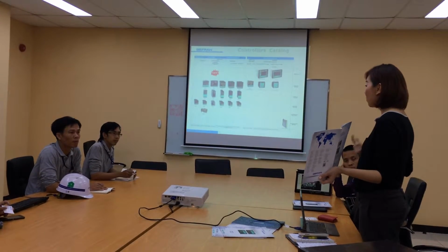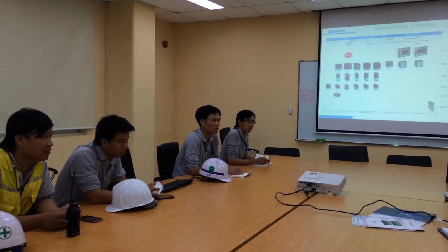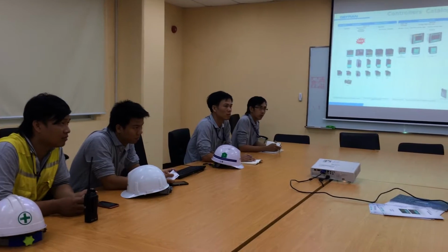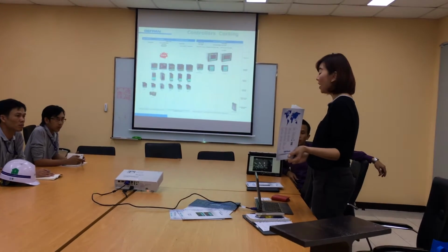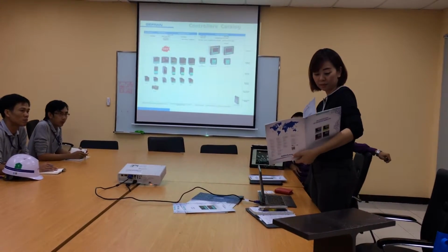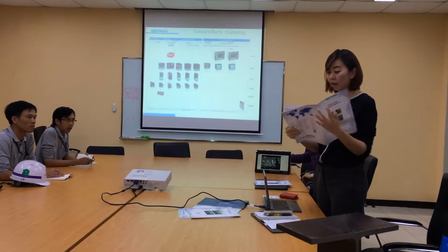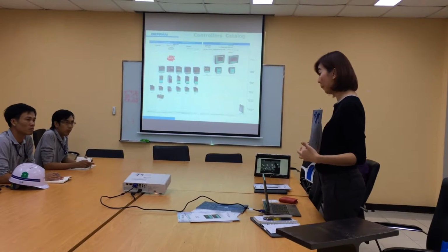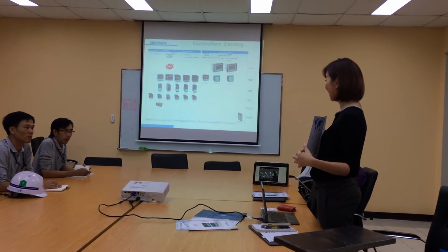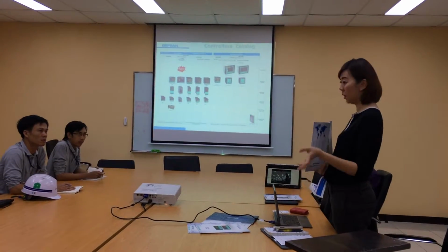This also comes with a maintenance and energy counter. Normally for your machine, if you need to count the energy, you need to get a separate controller with the CT, correct? But this comes with that function inside the controller as an optional function. If you want the energy counter function, you just add that option. It also comes with logic control programming, a 12-step logic block program, so it works like a mini PLC as well. All this comes as an option. You can choose to have it or not.